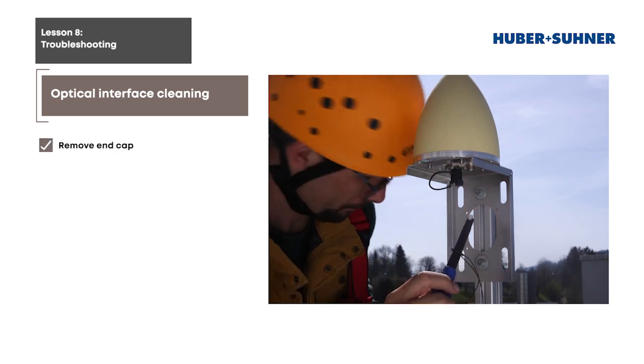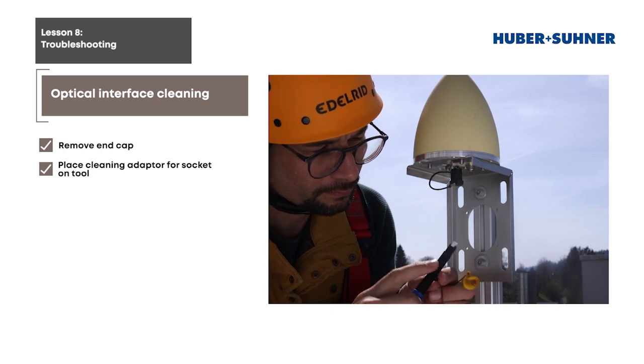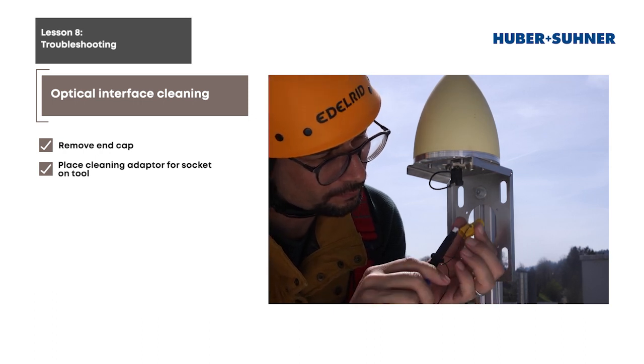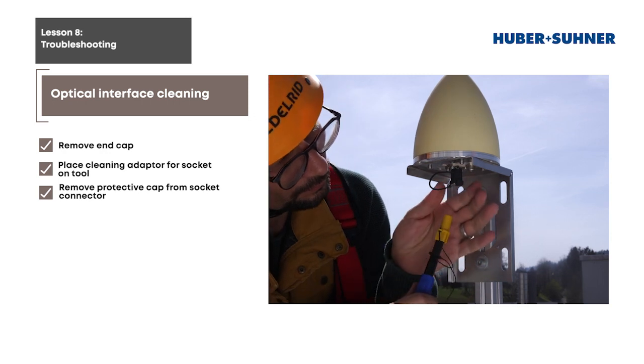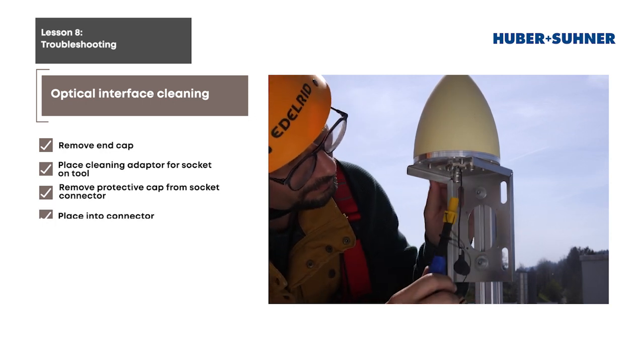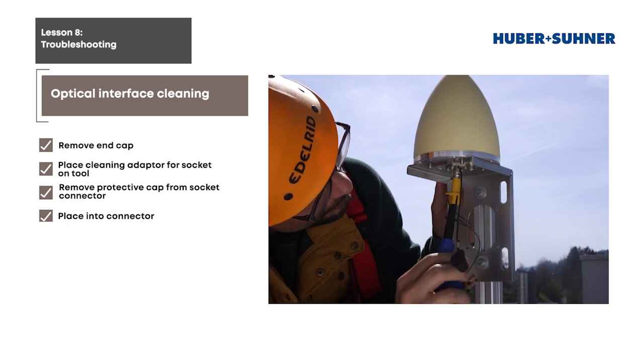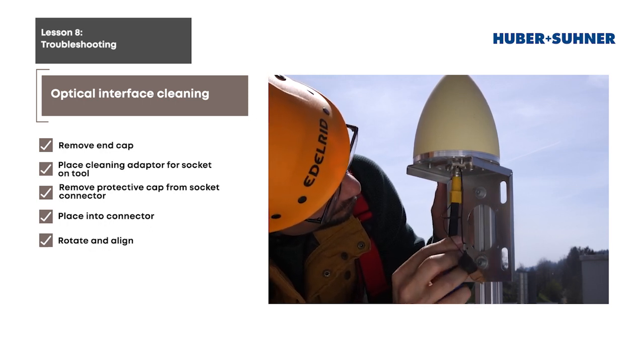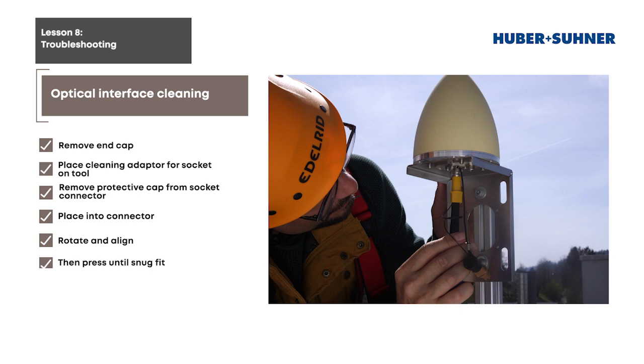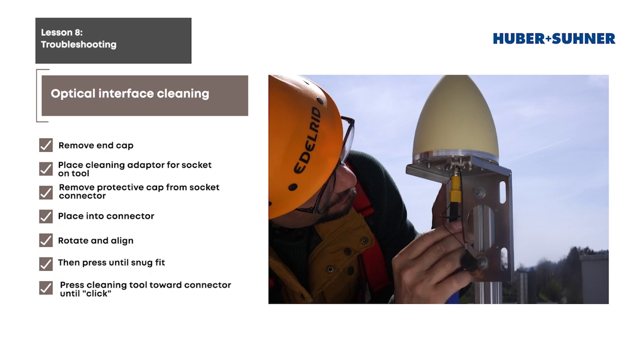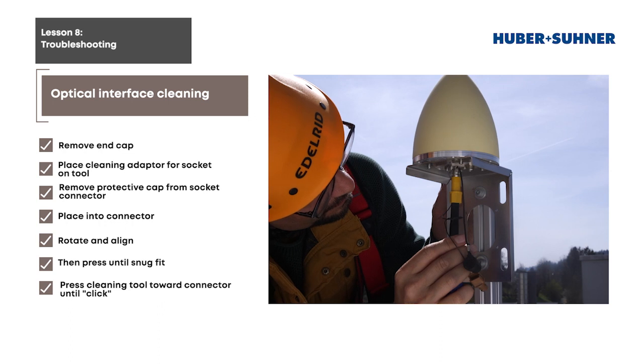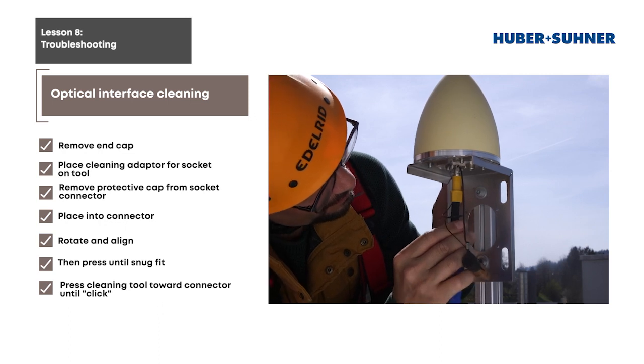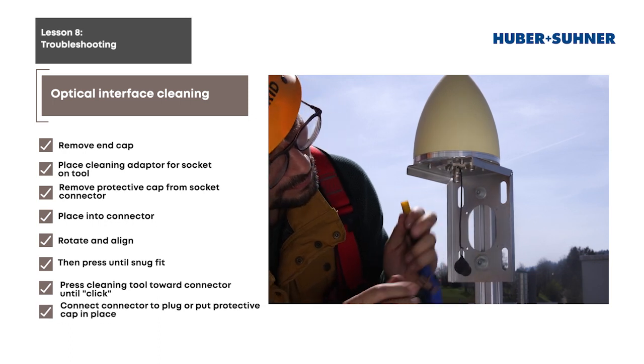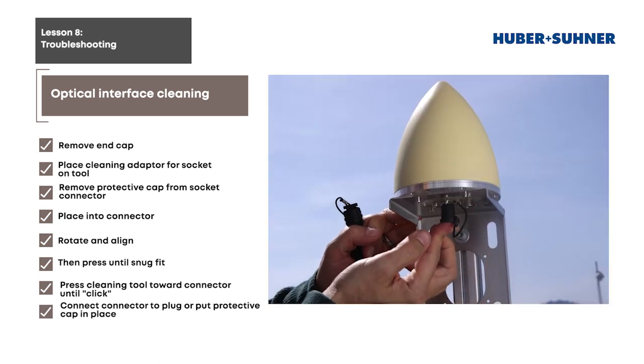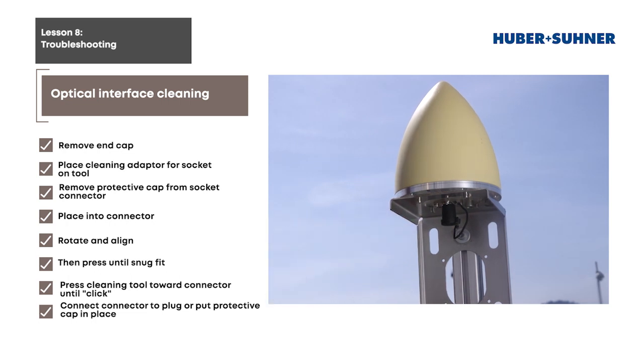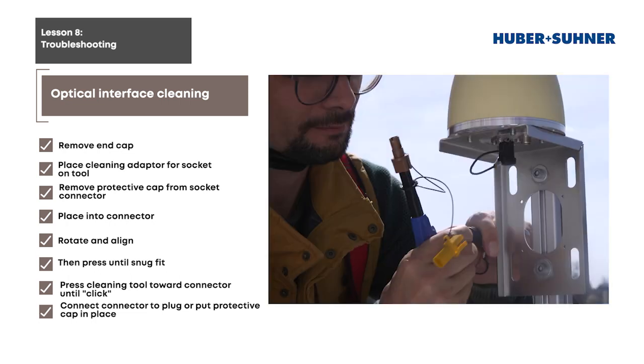Begin by removing the end cap from the cleaning tool and place the cleaning adapter for the socket connector on the end of the device. Remove the protective cap from the socket connector. Place the cleaning tool adapter into the connector, rotate and align, then press until there is a snug fit. Push the base of the cleaning tool toward the connector until an audible click is heard. Repeat. Finally, connect the socket connector to the plug or put the protective cap in place. Repeat all steps for the plug connector.